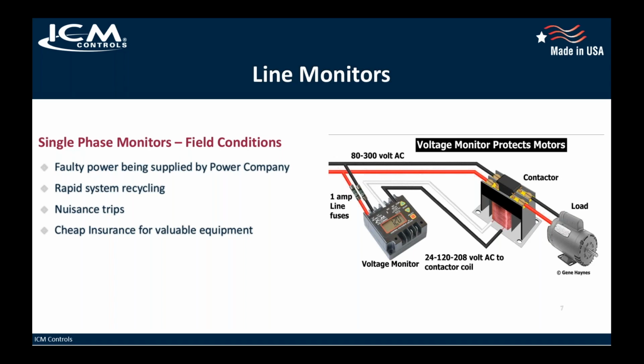And you see how we're connected to the coil, in this case of a contactor, across the normally open and common outputs. Basically what we're doing there is just monitoring that voltage. If we see a problem, over or under voltage, we're going to shut off the contactor, thus protecting your load. If for some reason you lost power and it came right back on again, that's rapid system recycling. We will have a user adjustable anti-short cycle delay that can be put on to prevent that short cycling. So this is a very good, cost-effective insurance plan to protect your motors.